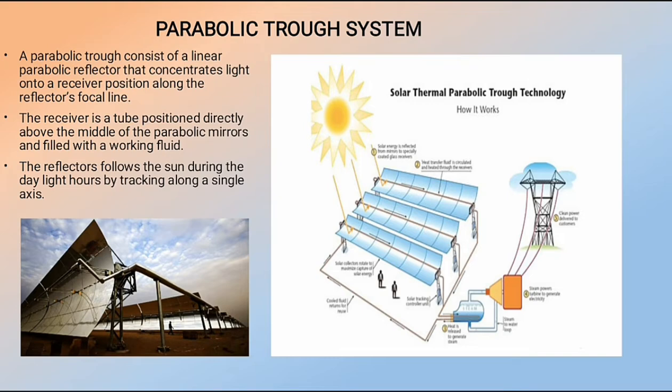The parabolic trough system is a single-axis tracker and line-focus system. Sun's radiation is incident on a linear parabolic reflector that concentrates light onto a receiver along the reflector's focal line. Working fluid passes through the receiver, becomes very hot, passes through a steam generator, and the highly generated steam drives a turbine where about one third of the heat is converted into electricity.